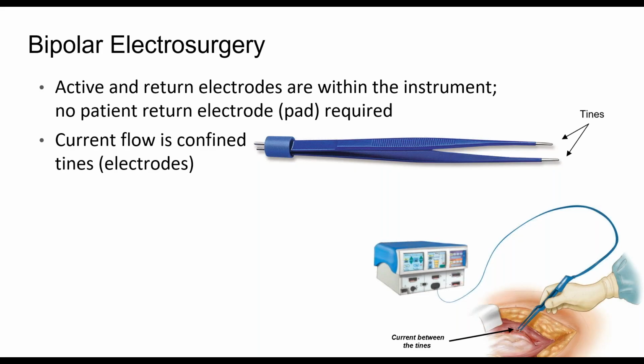And if somebody is wearing a pacemaker, you don't want electrosurgery going on with that. So if they're near that at all, they're usually using bipolar because of that. Because electricity isn't going to leave here and go scouting up there; it goes between here and here. As a matter of fact, in class, what we'd do is put that down on a piece of meat and just activate it, and it'd just fry everything in between the two tines.